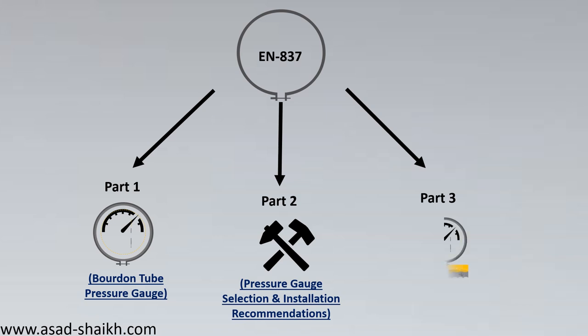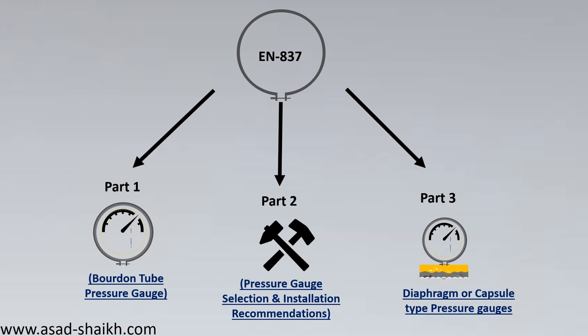EN 837 Part 3 deals with special types of pressure gauges — specifically diaphragm and capsule type pressure gauges. Here, diaphragm refers to the pressure sensing element within the gauge itself, not a diaphragm seal. Diaphragm and capsule type pressure gauges are generally used for low pressure applications. I hope you found this video valuable.